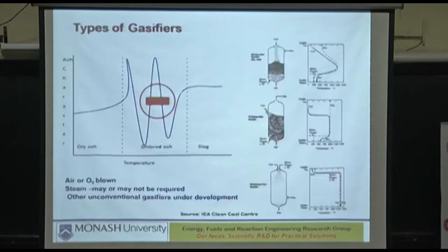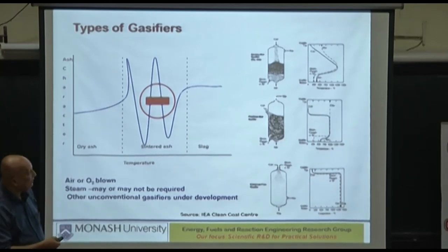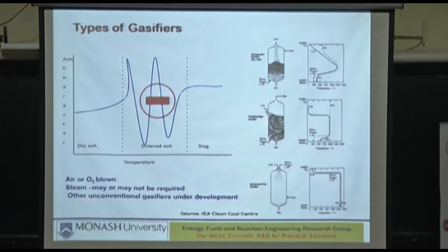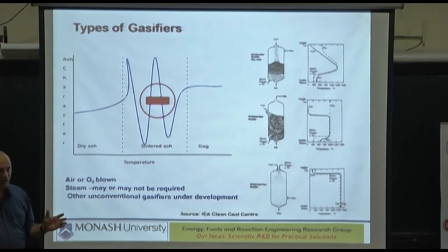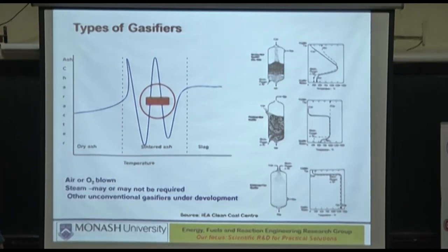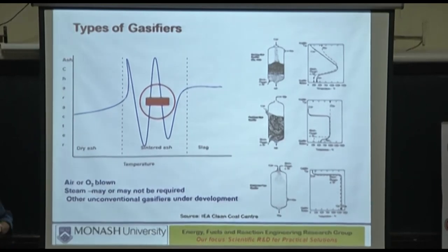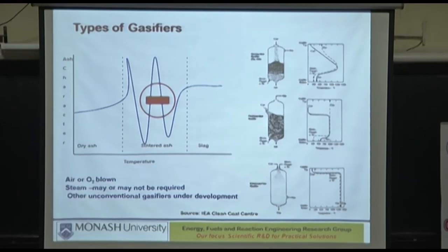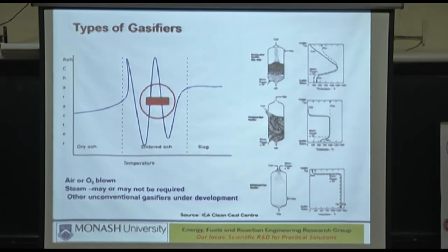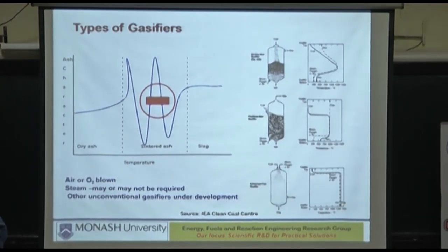The other important aspect is this. I've completely forgotten. This requires a very high starting particle size, large particles, 100 millimeters or so. But as you would expect, as that coal gets dried, pyrolyzed, then gasified, it will become smaller and smaller. So there will come a stage where the bottom layers are predominantly smaller ones and the upper layers are predominantly larger ones. You get a mix of that, and if they get too compressed because you are not able to do the ash extraction effectively, then you have a problem. So the fixed beds are actually prone to clogging, irrespective of what the technology providers say.